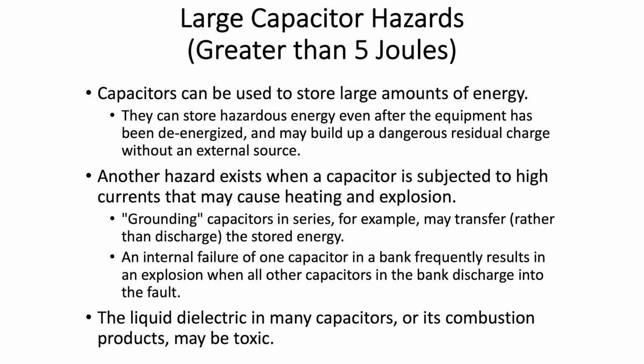So large capacitor hazards, storing energy, large amounts of energy, even after the equipment's been de-energized upstream, it can build up a dangerous residual charge without an external source. Okay? So with capacitors, as part of my lockout tagout, I want to make sure after I disconnect, I discharge the capacitance, that stored energy, into the ground, into the air, both, whatever means we're using. Another hazard exists when a capacitor is subjected to high currents that cause heating and explosion. Grounding capacitors in series, for example, can transfer rather than discharge the stored energy from one into the other that already is full, and then bad things happen.